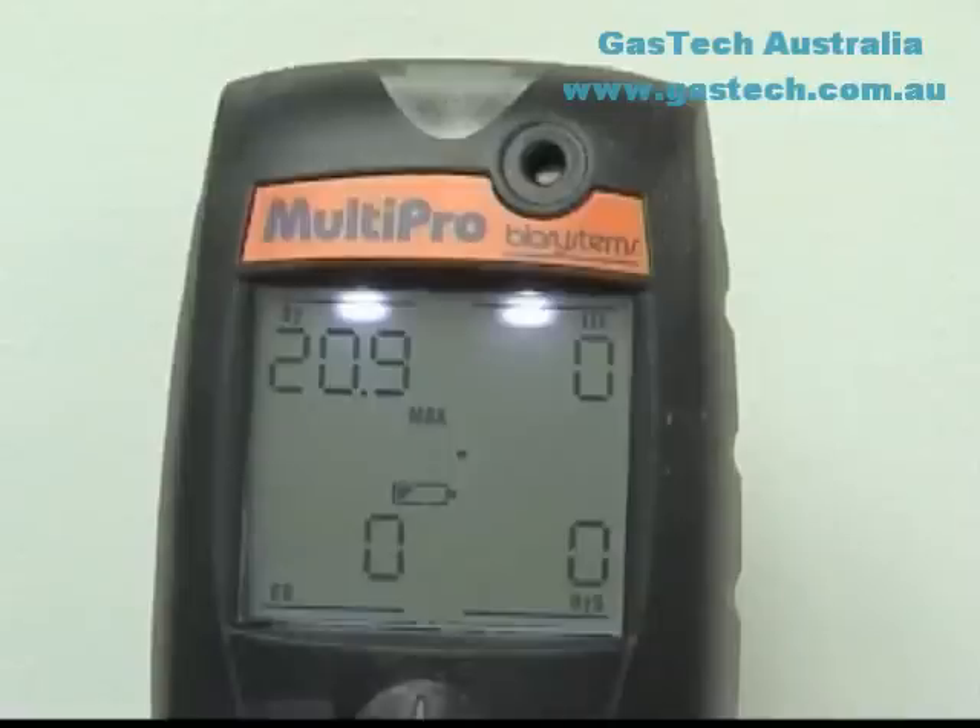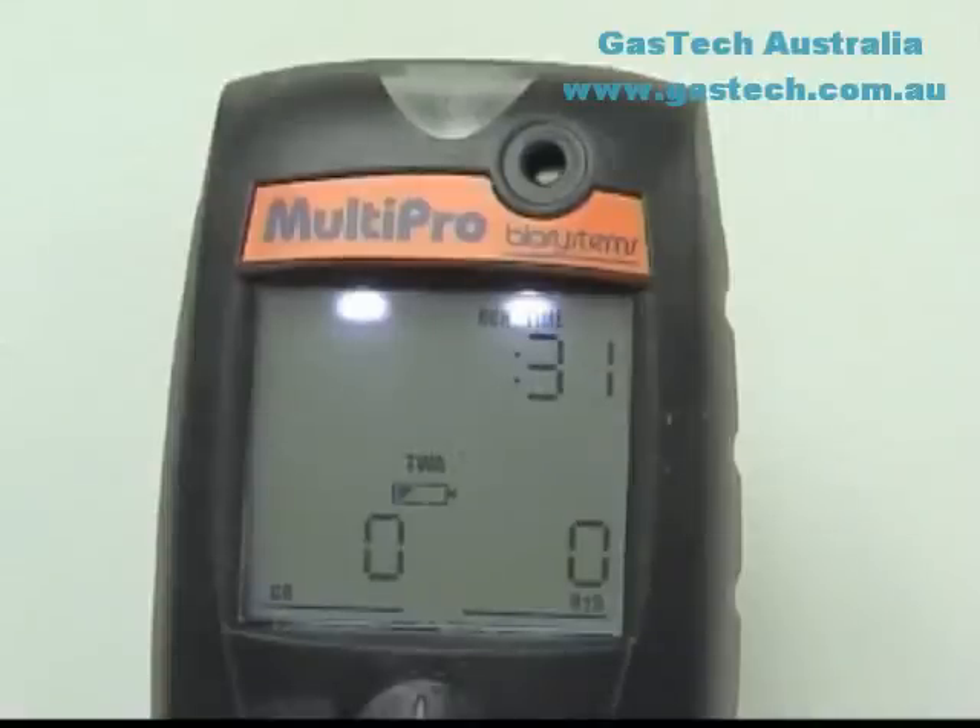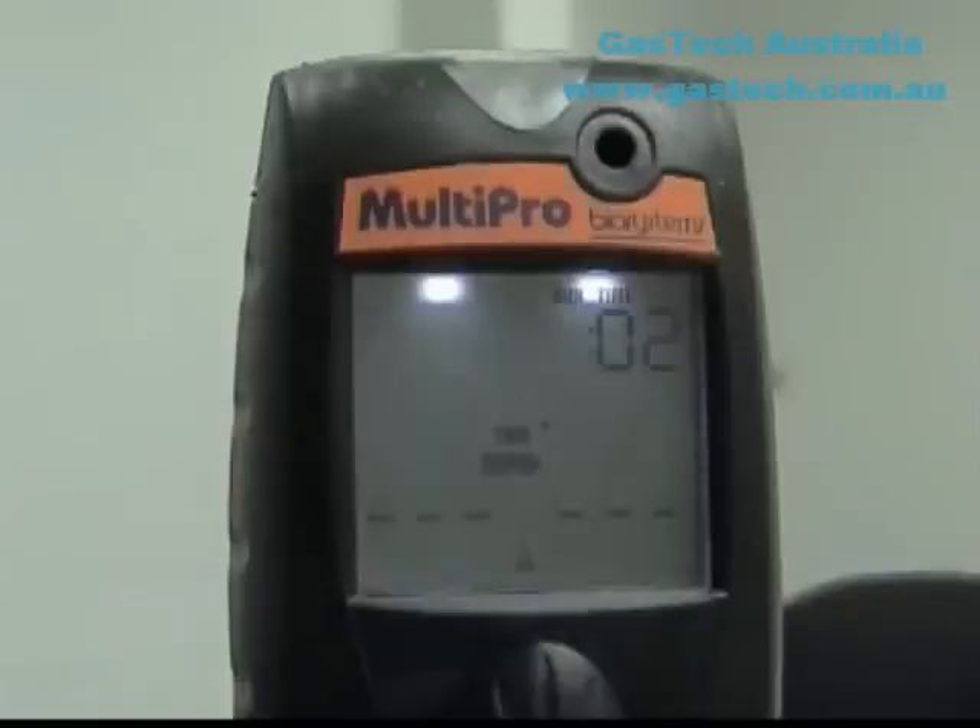The Max Readings represents the highest readings registered by the instrument during the current operating session. Pressing the Mode button a third time will show the STEL screen, and a fourth time will show the TWA screen. The MultiPro must be in continuous operation for at least 15 minutes before it will be able to calculate TWA values. For the first 15 minutes, the screen will show the length of time that the instrument has been operating instead of the TWA values.